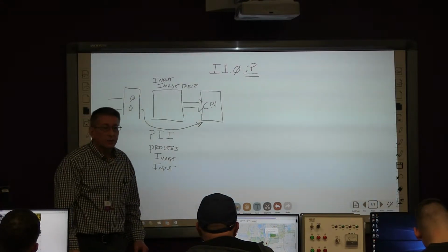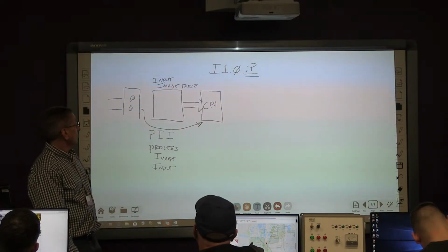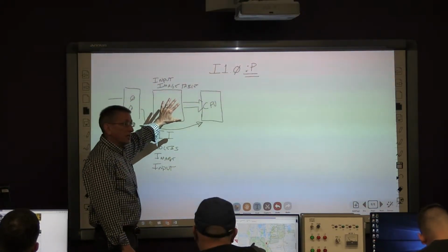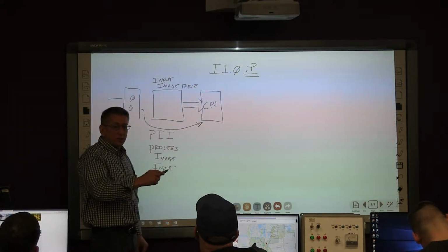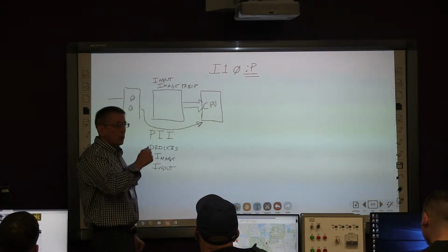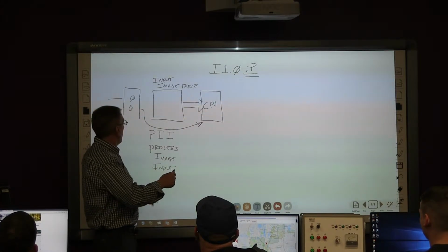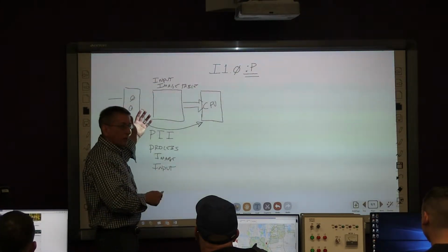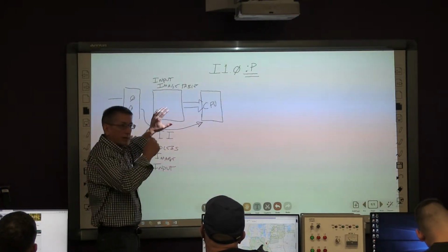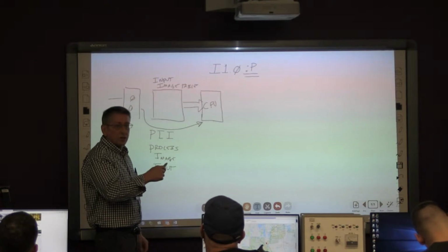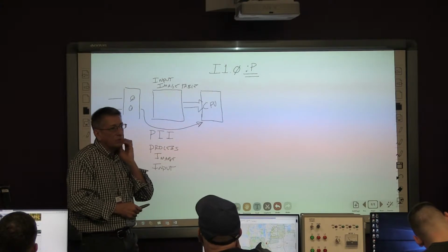the input module. The reason you might want to do that is what happens with the image tables is they only get updated every scan. Whatever the length of the scan time is, the image tables get updated once per scan, right? But we could have a fast changing input that might be changing before we get through a complete scan, right? So this way the CPU goes directly to the input and grabs the data right from the input module.